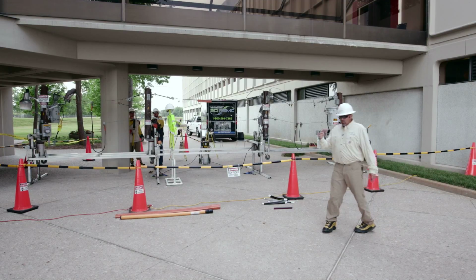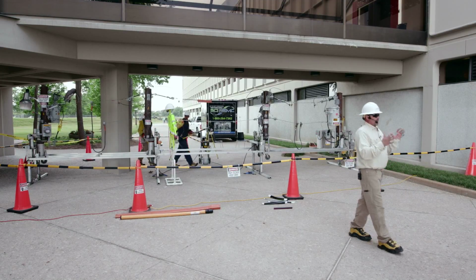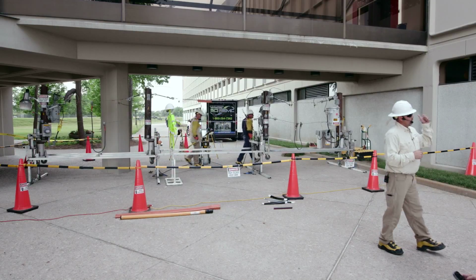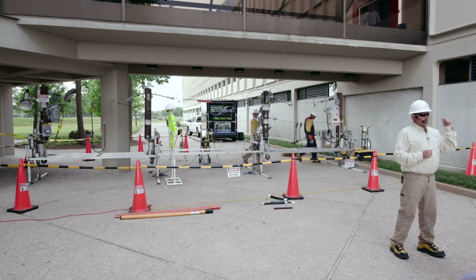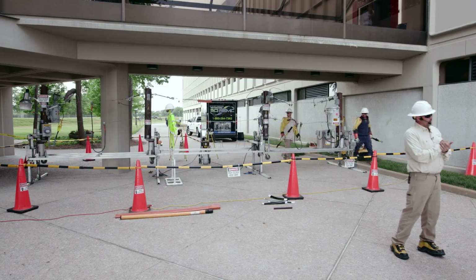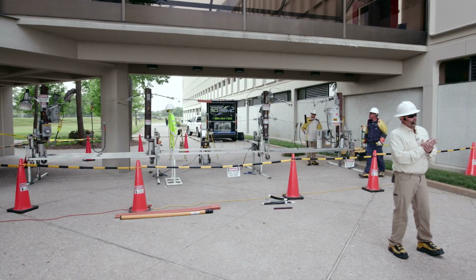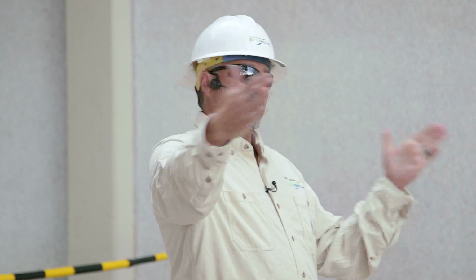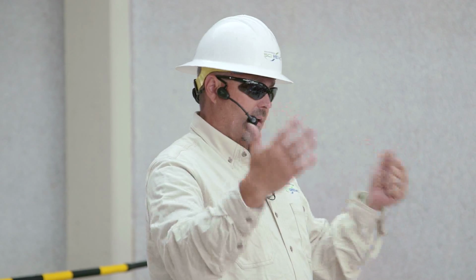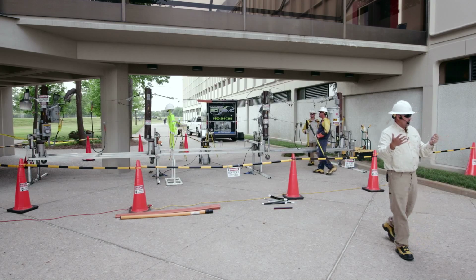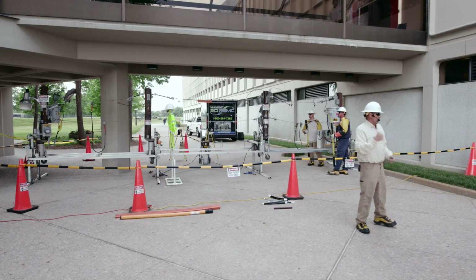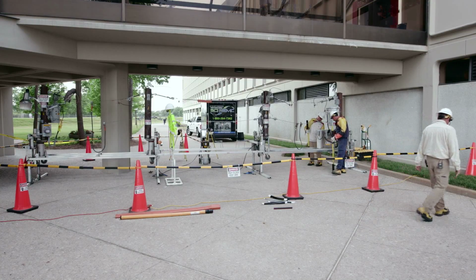So what we do now is put a very similar fault on that same recloser. You'll hear it click, open up, click, open up, and then after that last third one, it's going to give a long burn curve — like it's going to try to burn it off one last time. You'll hear it here. Clear.